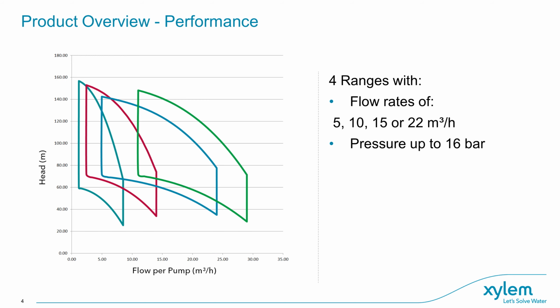In terms of performance, each pump can be sized to achieve a flow rate ranging from 5 cubic meters per hour all the way up to our biggest reduced space version ESV with a design flow rate of 22 cubic meters per hour. The sets can also achieve a closed valve pressure of up to 16 bar. So as you can see from the performance chart, the GHVR can be sized for a wide range of water boosting applications.